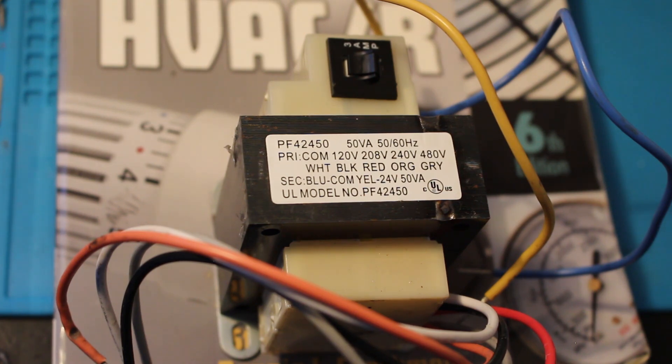Most transformers used in the air conditioning and refrigeration field are known as isolation transformers. This means the primary and secondary windings are magnetically coupled but electrically isolated. The most common transformer used in this field is a step-down control transformer.